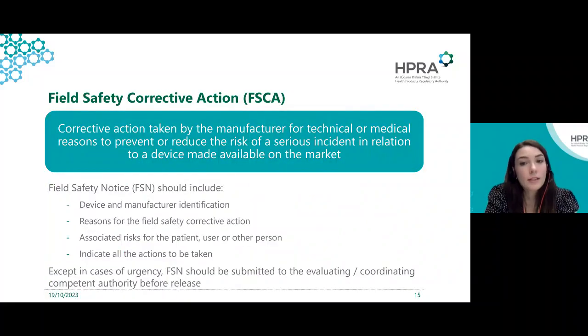A field safety corrective action is an action that the manufacturer takes to prevent or reduce the risk of serious incidents in relation to a device that's already on the market. FSCAs may involve a product removal, a recall, a field modification, software updates, instructions for use updates, or user training, or a combination of these.